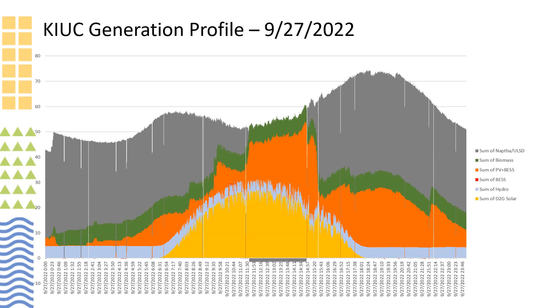And here you'll see a little bit of gray right there. That's not a typo. When we run in synchronous condensed mode, we're spinning our generator, but there are windage losses because of the LM2500 still spinning the turbine. So we still incur about a megawatt and a half of losses there.